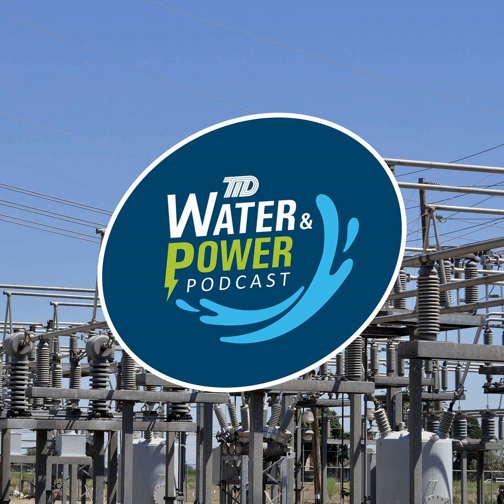So a ring bus means that the lines will come in and essentially create a loop within the station itself. It allows load serving capability to come from one side of the station or another, and it also has protection on our transformers. The main reason that we have the ring bus is reliability, like I mentioned. Instead of having one breaker that the line feeds into, the line will actually feed in between two breakers. These breakers are set up like a ring, which is why it's called a ring bus. That allows us to work on one breaker or the other, and the line is still able to serve the load in that area or even loop through the other line.